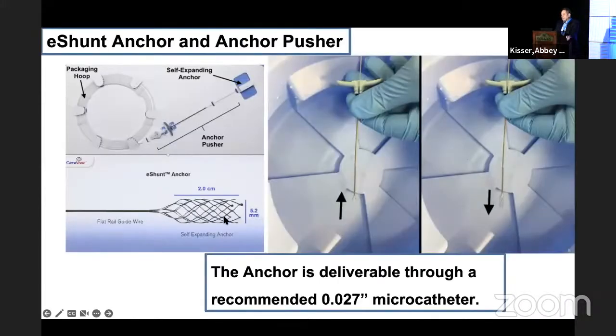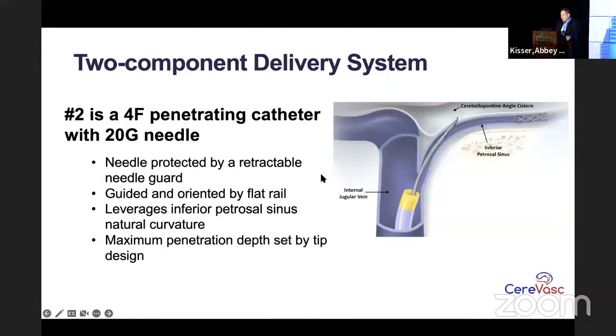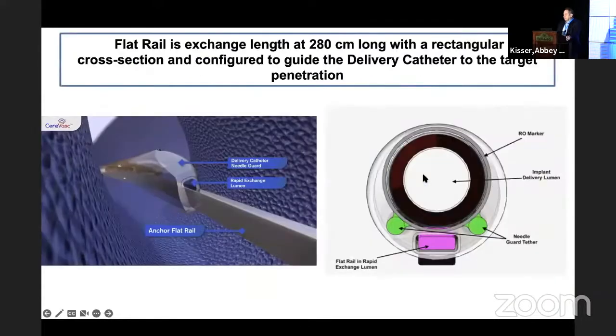This is what the anchor looks like, and what's special about it is it has a flat rail, which enables a very low profile for the system. And the second part of the system is this delivery catheter, which has a needle on it, which is protected by a guard that effectively enables us to navigate it into position and then retract the guard when at the target position, gently enabling us to advance through the dura into the CP angle cistern to deliver the e-shunt. The e-shunt itself is preloaded inside the needle.